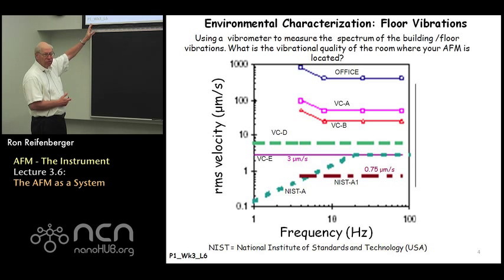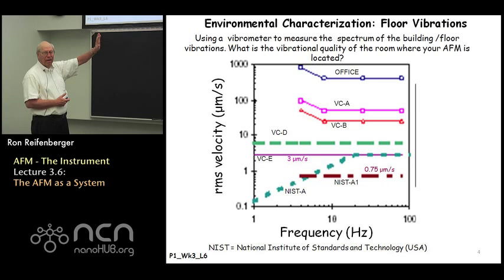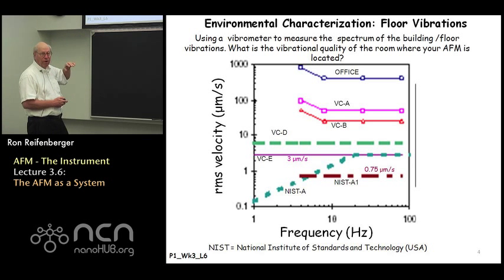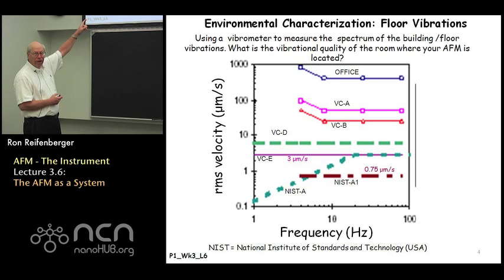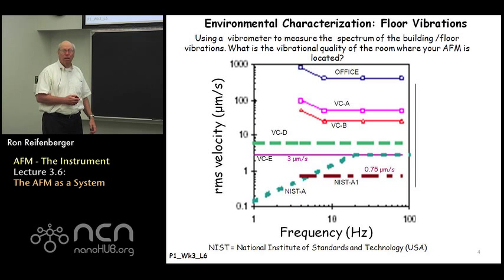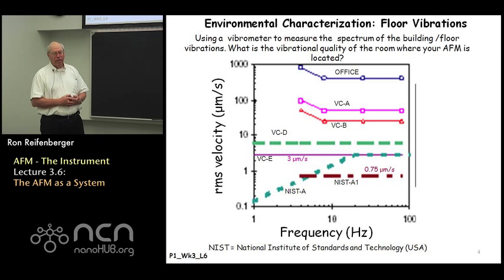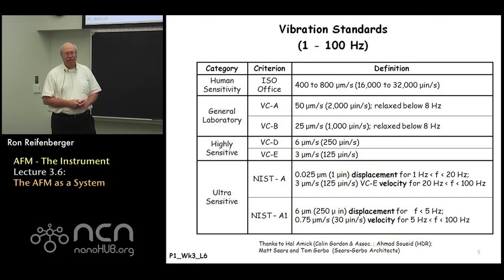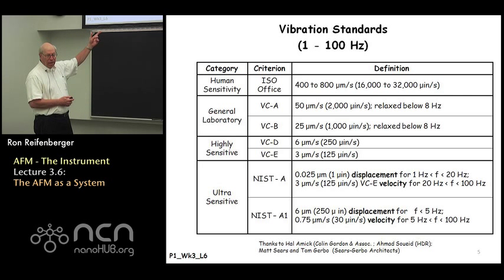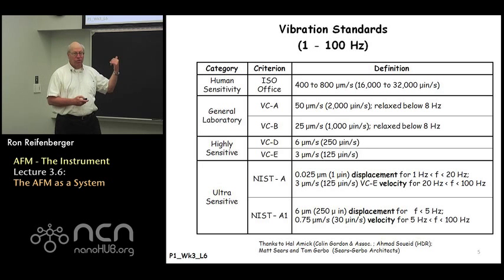The frequency of vibrations goes from on the order of one to on the order of 100 hertz. Above 100 hertz you start to talk about acoustic vibrations — acoustic noise coupling into your instrument. Frequencies below 100 hertz are characterized in terms of floor vibration levels. If you can achieve the so-called Vibration Criteria E, the VCE level — basically three microns per second vibration of the floor over the entire frequency range from one to 100 hertz — then you have a very good, very quiet lab to work in. I also provide the vibration standards in table format for future reference.